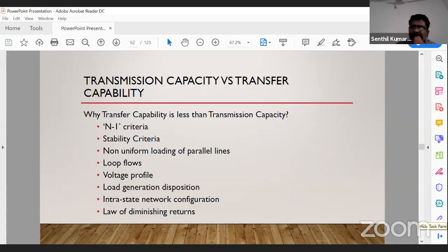So how much are we going to allow? In this perspective, our Central Electricity Authority has issued the transmission planning criteria book, with norms and conditions on how the voltage should be maintained, and how the transmission conductor-wise capacity surge is allowed. They segregate this into three different categories: surge impedance loading, voltage limit, and thermal limit. Based on these conditions, they set norms such as the N minus one criteria, stability criteria, non-uniform loading of parallel lines, loop flows, voltage profile, load generation disposition, intra-state network configuration, and law of diminishing returns.